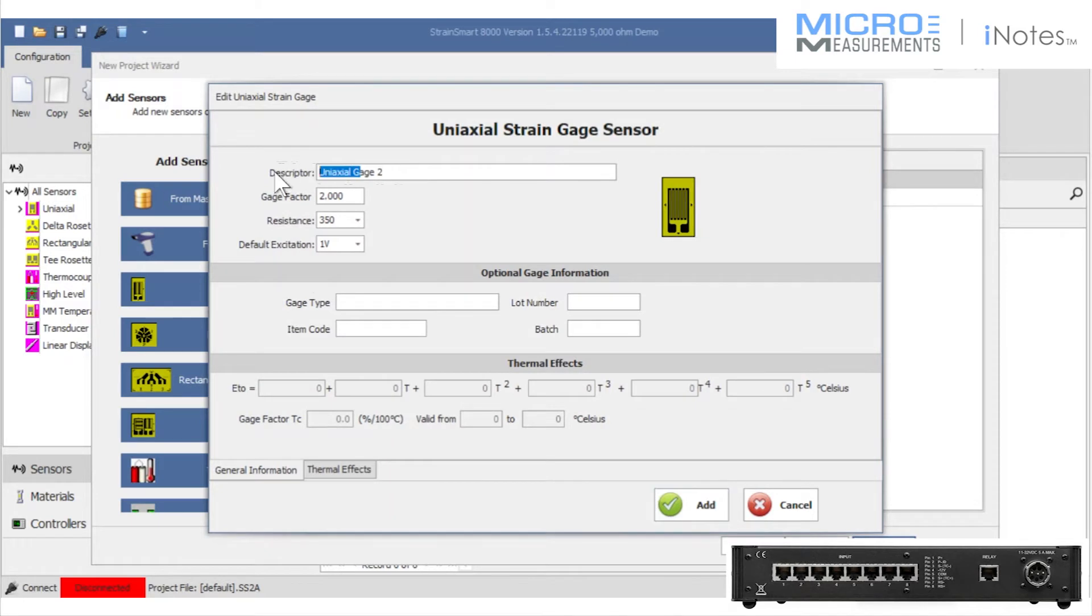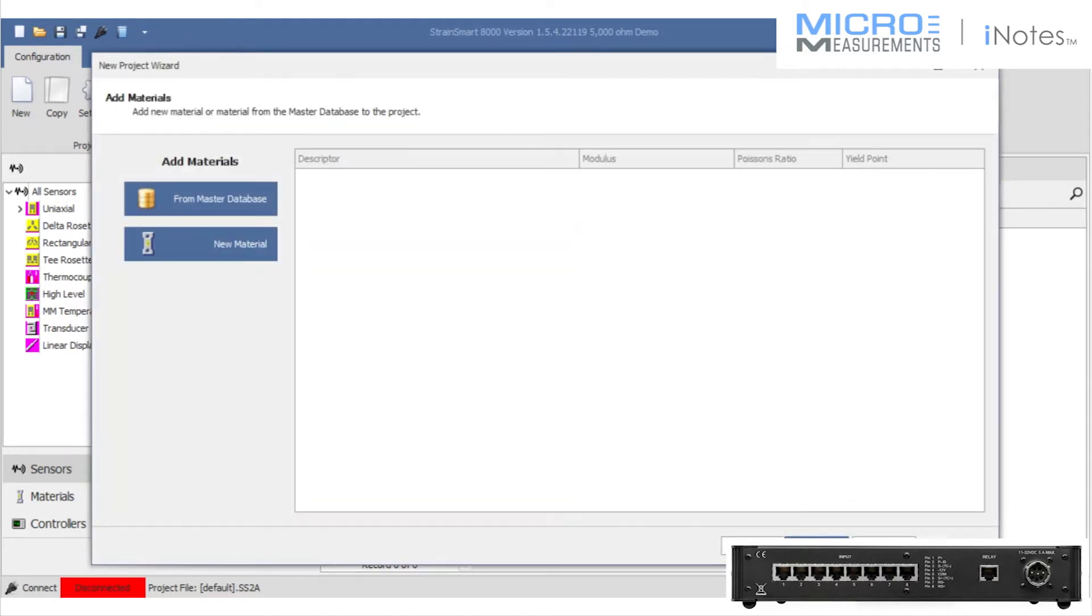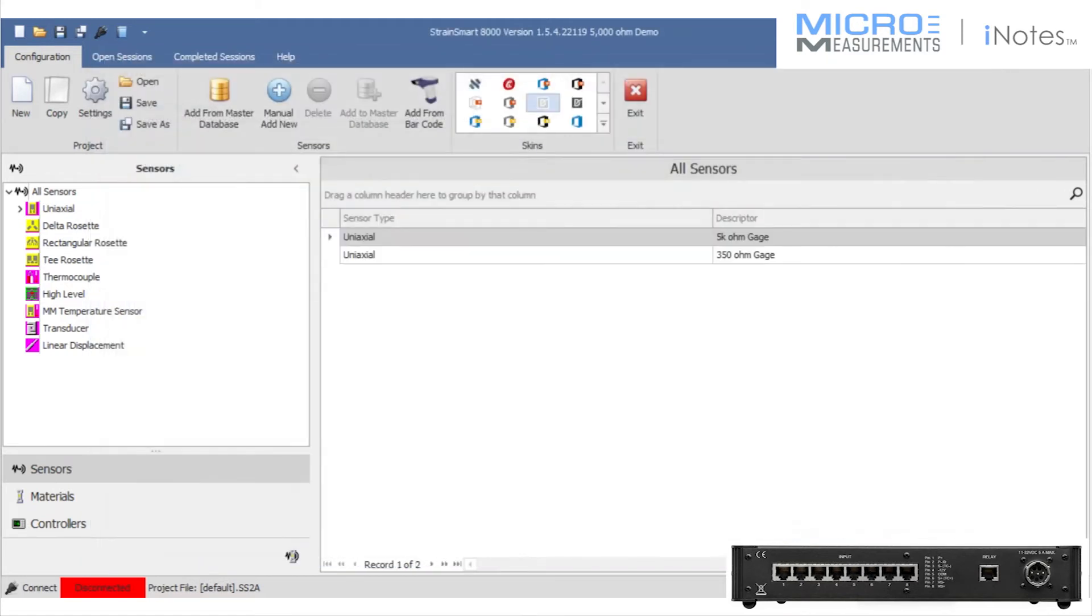I'm also going to add a 350 ohm gauge on another channel. I'm going to leave gauge factors at 2 and keep the excitation voltage low at 1. And that basically is going to complete my connection or my setup to the scanner for my sensors.